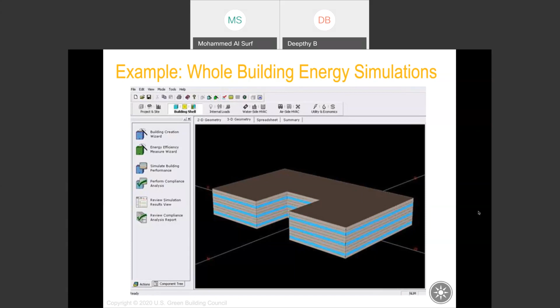It's also important when we do the whole building energy simulation, this will enable the project team to establish an energy performance baseline by using the model that meets the minimum requirements of the energy code or standards, such as ASHRAE 90.1. It also identifies and prioritizes energy conservation opportunities by evaluating trade-offs between capital and operating costs. So the model building is built in a computer program per requirements of ASHRAE 90.1.